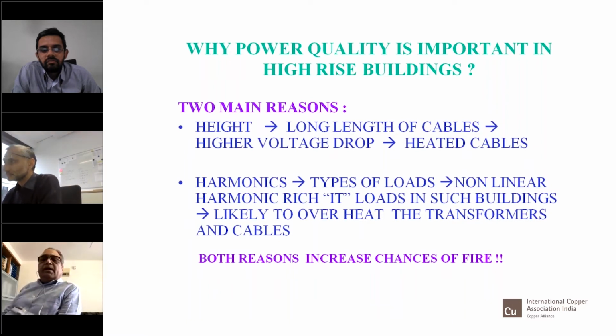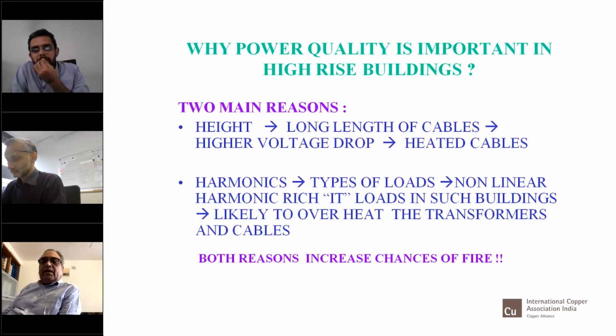Most new high-rise or commercial buildings, as Mr. Bakshi also said, have non-linear loads - a lot of IT loads, computers, servers and related equipment. These harmonic-rich loads are likely to overheat the transformers and cables used in the building if the harmonic levels reach a very high level.